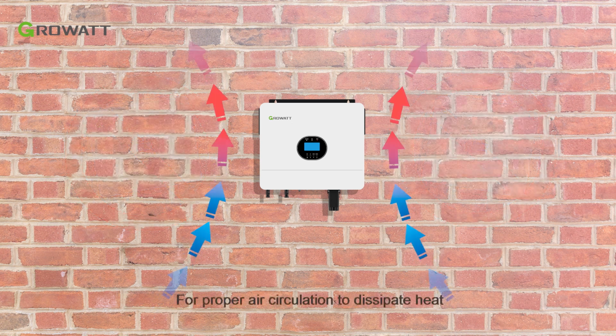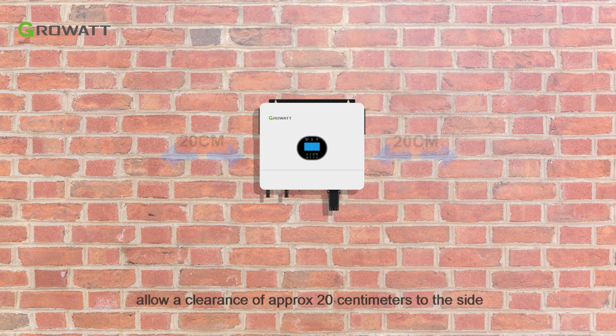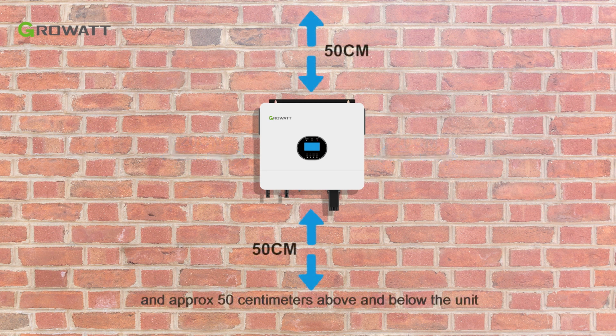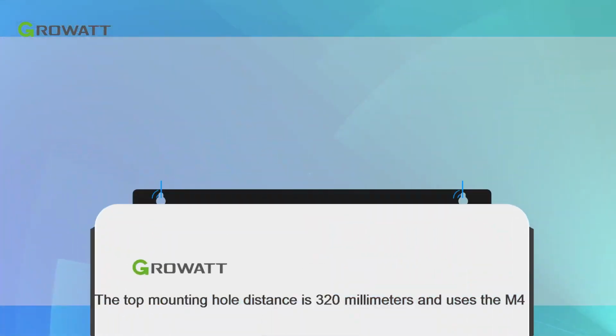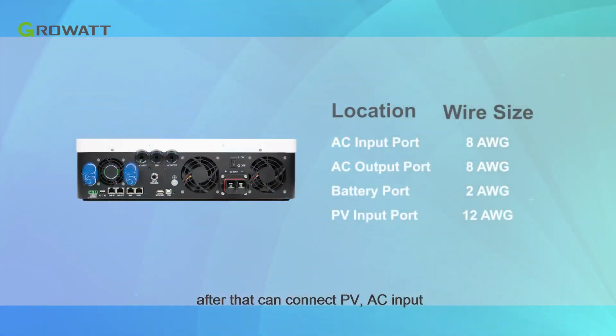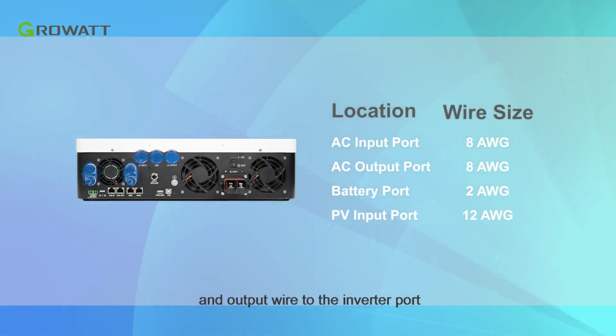For proper air circulation to dissipate heat, allow a clearance of approximately 20 centimeters to the side and approximately 50 centimeters above and below the unit. The top mounting hole distance is 320 millimeters and uses M4 screws. After that, you can connect the PV, AC input, and output wires to the inverter ports.